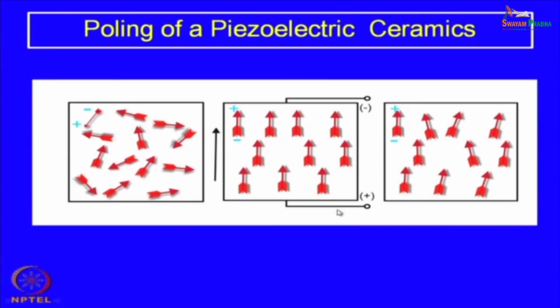So, poling is normally done slightly below the Curie temperature, where the movement of the dipoles becomes easier. There the kinetics of the process is faster close to the Curie point. So, poling is normally done in a warm environment, normally in a liquid oil, close to the Curie temperature, and then you apply a relatively high voltage for a long enough time, so that you allow sufficient time for the dipoles to align themselves with the direction of the applied field. That is the process of poling, which regularly has to be done for any kind of piezoelectric materials or piezoelectric ceramics.